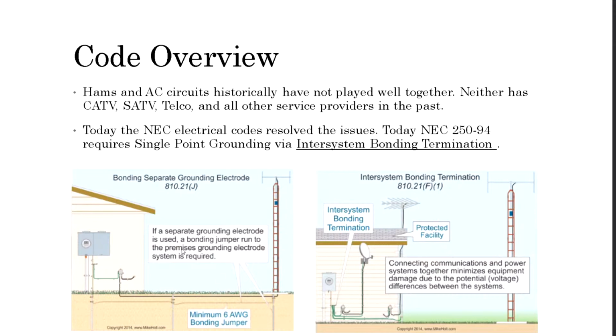Here's a real simple system. We've got our tower. We've got our service entrance. You can see our ground electrode system here. And you can see our coax coming in up to right here where the surge protector is, a ground wire going to the GEC, back to the ground electrode system, and the coax going inside. The picture on the right, just a little more detail with three antennas, but it's all showing basically the same thing. The only thing we're modifying is we're taking it one step further. We're not using wires to make these intersystem connections. We're going to place a bus bar right out here underneath our meter, or wherever this GEC conductor is going down into the dirt from our electrical service. You can see it here in this picture. You can see it again here. This is where we'd want to place our ground bar to mount everything instead of using wires.